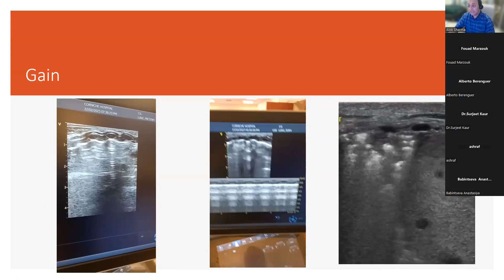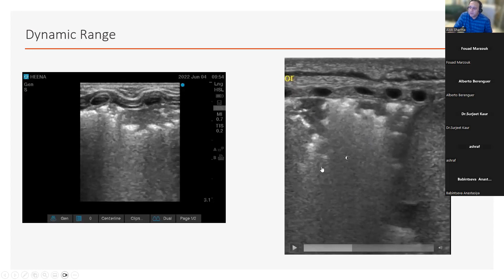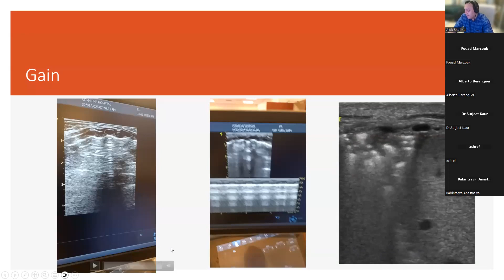Really, what I want to see is this tissue. I want to see the sound waves interact better with this tissue. And this is a depth of about 4 centimeters. So what I've done is I've just increased my dynamic range. Now, for all of you, what I need you to do over the next 10 days is to play with your machines while you're getting your images to try and get this. And this is just an example of dynamic range. So here we're using a low dynamic range. Because we're using a low dynamic range, our image is quite blurred. I would say it's quite grainy. Whereas here I'm using a higher dynamic range, which means that we're interacting with tissue better. So this is giving me a much better tissue image.